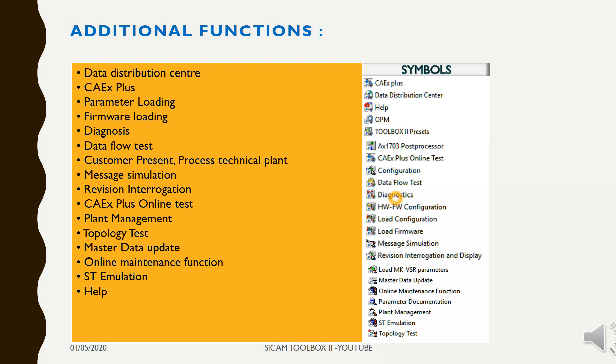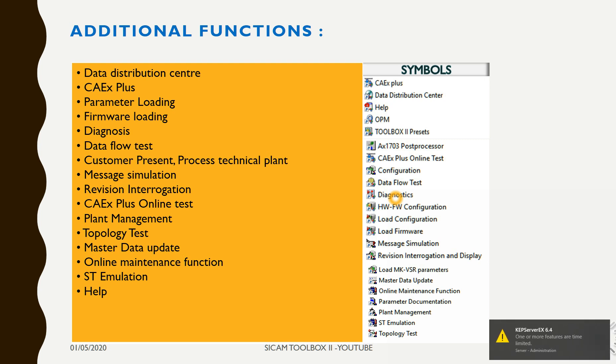CAEx Plus is where you can write logics according to IEC 61131-3 within the automation unit. You require a hardware key to access the module. Parameter loading is used to download the complete configuration into the automation unit. Firmware loading is used for firmware updates of automation unit modules. Diagnosis allows you to see errors within the automation unit and communication station failures.